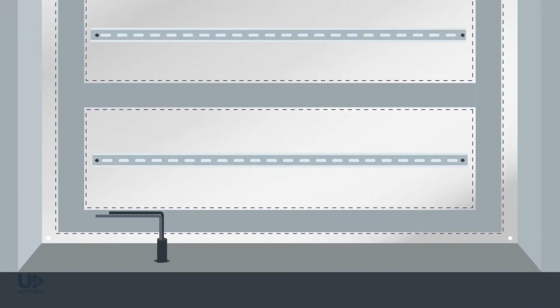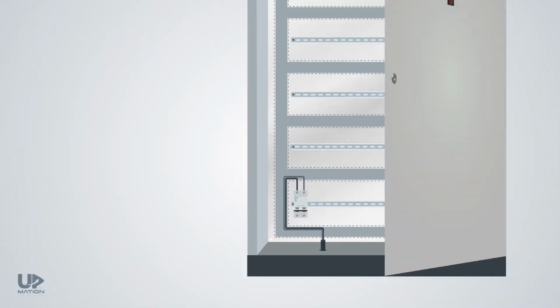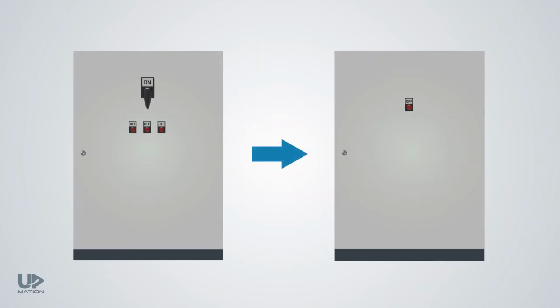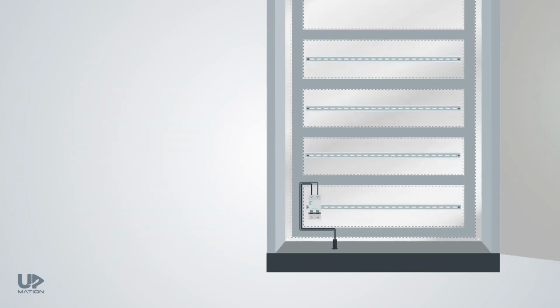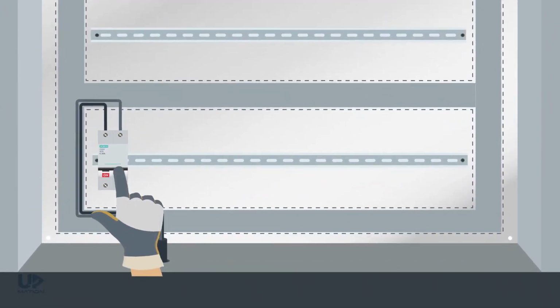Now, assume our single-phase power is entering a two-pole miniature circuit breaker, or MCB. This electric power comes from another panel within the electrical room, like a kind of low-voltage power distribution panel. Either way, the MCBs are a type of protection circuit breaker that are used at the entrance of the panels with different consumptions up to 25 amps. They protect our panel from overload and short-circuit faults. Furthermore, we can connect and disconnect the whole power to the panel manually using this MCB.